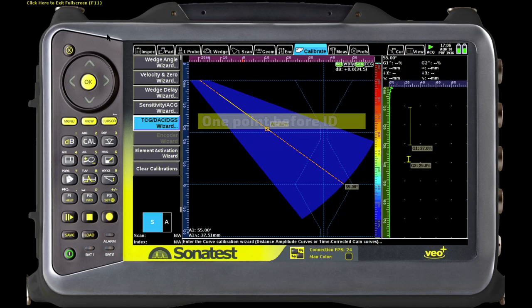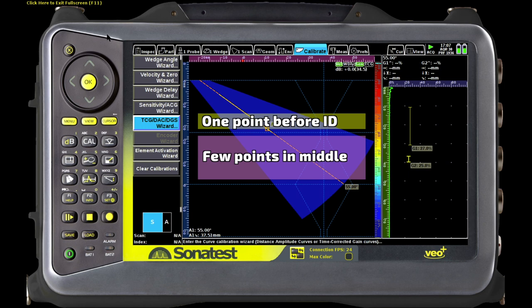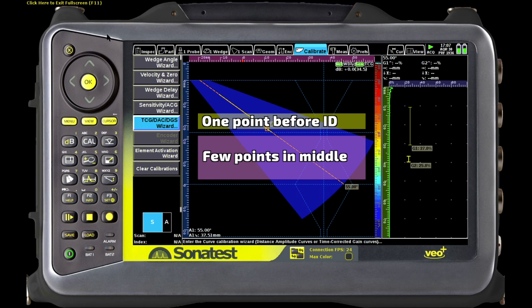We need to establish the sound path range that we're going to use for calibration. We're using the high angles to inspect the ID of the pipe and the low angles to inspect the OD, so we need calibration points beyond those. We need a calibration point before the ID of the pipe and after the OD. So we need to start at the three quarter T hole and go all the way through the thickness and then hit the quarter T hole again, which would represent just a point just past the OD.